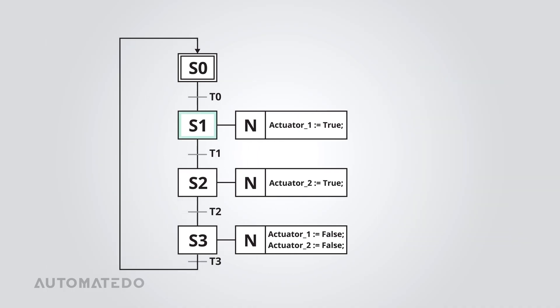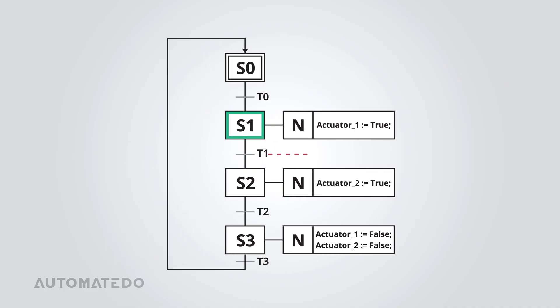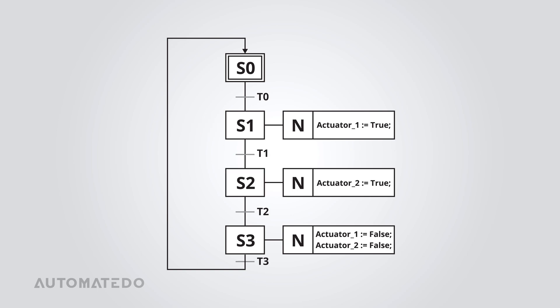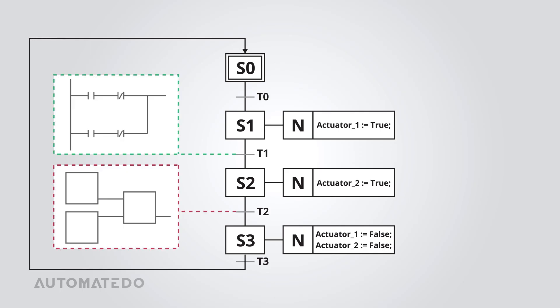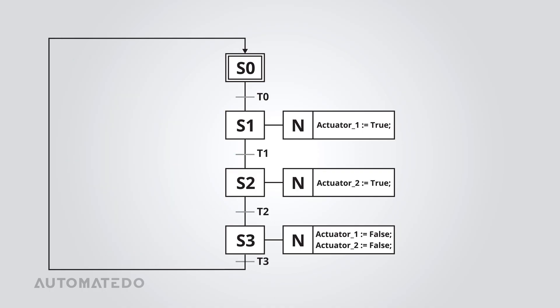Then, there are transitions which act as decision points. When a transition condition is met, the next step is activated and the previous step is turned off. You can use any PLC-compliant language to program transitions, but ladder diagram and function block diagram are more common here.